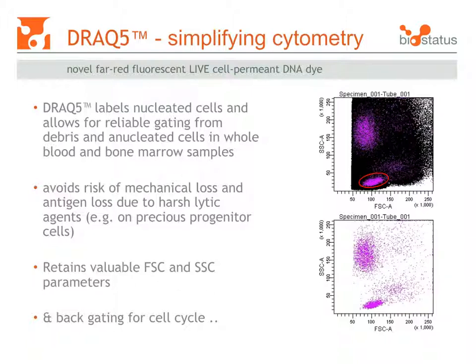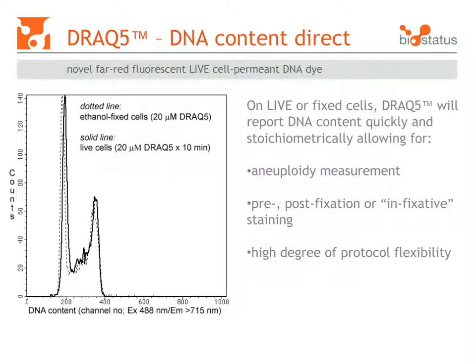DRAQ5 allows gating of nucleated cells from enucleated or damaged cells in complex biological samples such as blood and bone marrow, without the need for time consuming and often damaging sample preparation procedures such as centrifugation and red cell lysis. It reports DNA content in cells with stoichiometry to permit cell cycle and aneuploidy analysis as performed by flow cytometry.